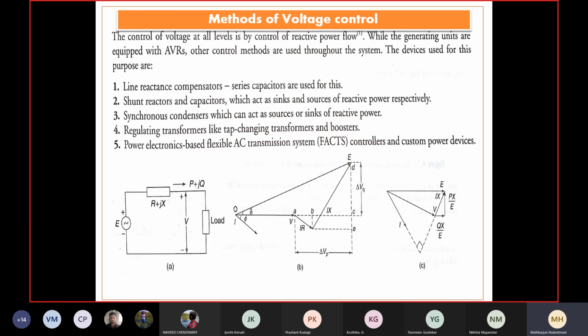The other is the rotating machine, the synchronous condenser, which can act as a source or sink of reactive power. For this I was narrating an example: a synchronous motor running with zero mechanical load. There is no load on the shaft, it is running free, and with the control of excitation, in the highly leading and highly lagging, or overcompensated or undercompensated mode of that excitation, it supplies and absorbs reactive power. So this way the synchronous condenser can act as a source when it is overcompensated or overexcited, and it is absorbing reactive power when it is underexcited.